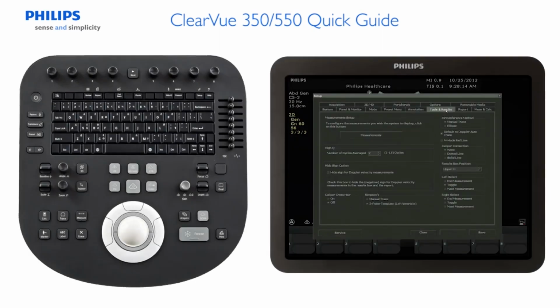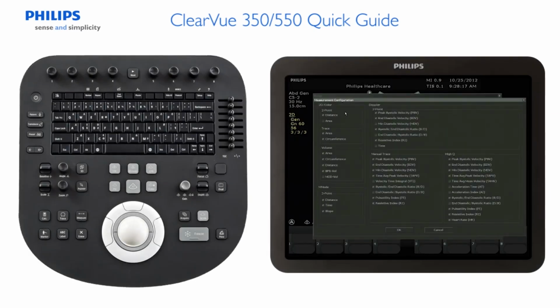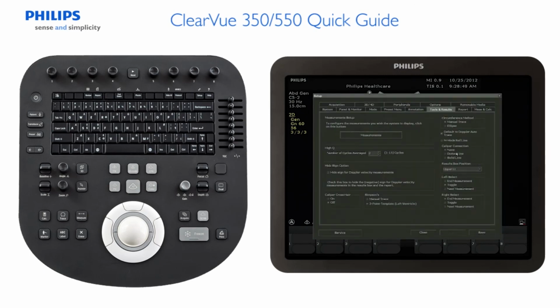In the Tools and Results tab, click Measurements, then configure the display for the unlabeled measurements in each imaging mode. For example, in 2D and color, you can select whether you want the caliper to display distance or area. In M mode, you can select whether you want the caliper tool to display distance, time, or slope when measuring M mode. This is also where the Doppler results are selected for 2-point measurements, high Q, and manual trace. Other key setups include caliper connection line choices, results box placement, and the left and right trackball button functions to toggle or end measurements. When you are finished altering the settings, click Apply.